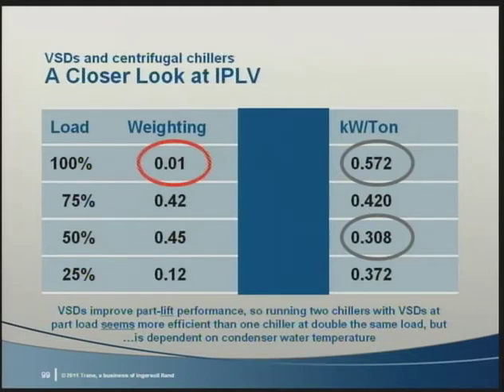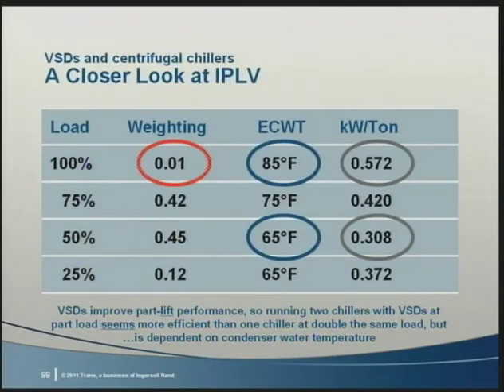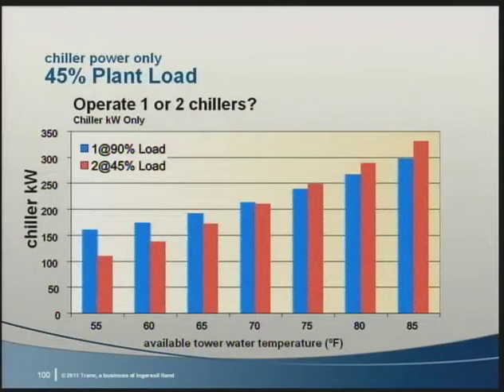Here, the 50% load value of 0.308 kW per ton has a commanding efficiency advantage over the full load value of 0.572. But the 50% load number has condenser water that is 20 degrees colder than the full load number. Of course it looks more efficient. Its lift has been reduced, especially since, as we discussed earlier, variable speed drive chillers are part lift devices. We need to compare those chillers at the same condenser water temperature. So let's do that. The results for a system at 90% load, with the condenser water temperature shown, are represented here on the table and include only the chiller kW.